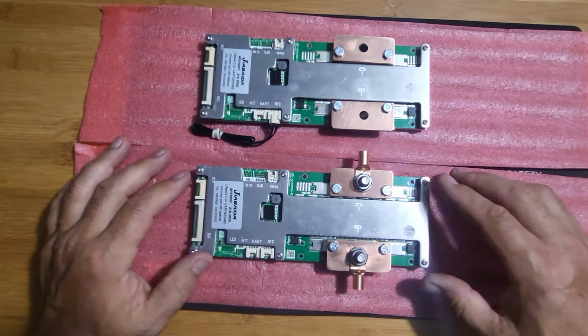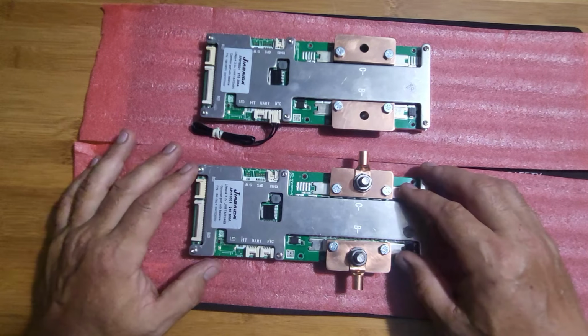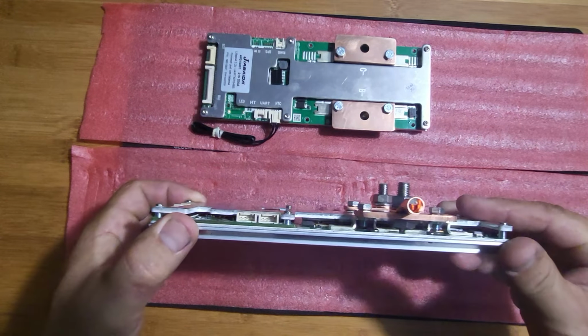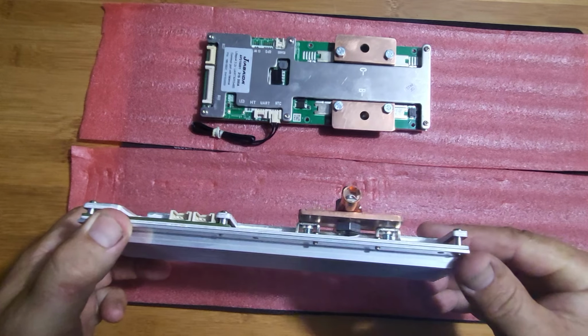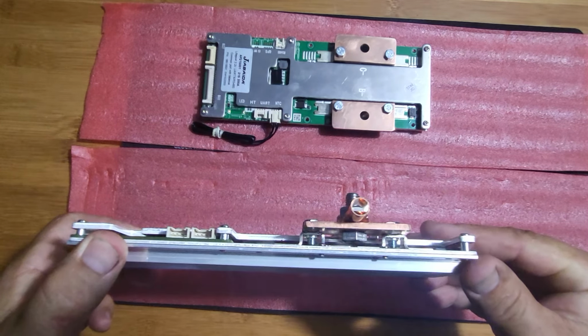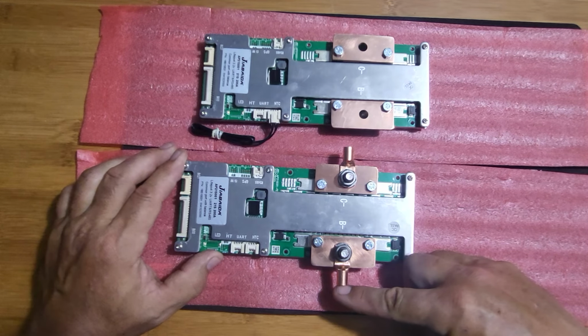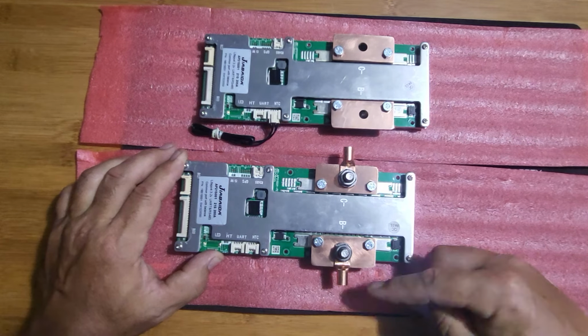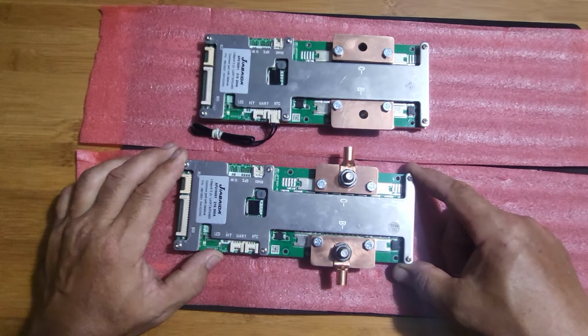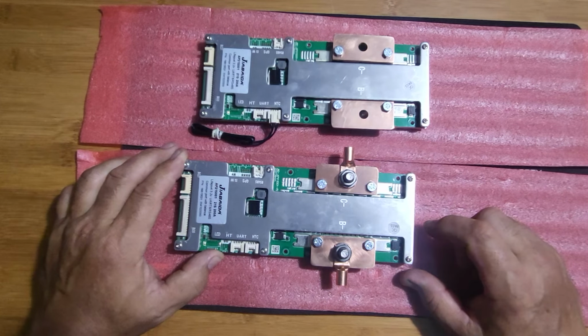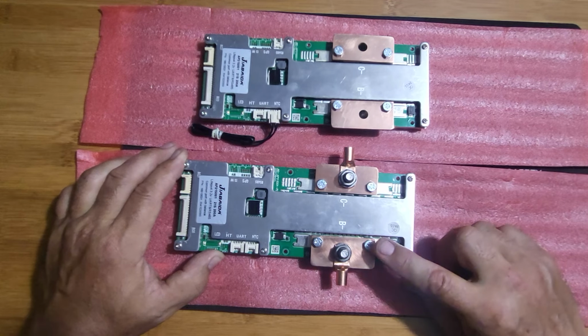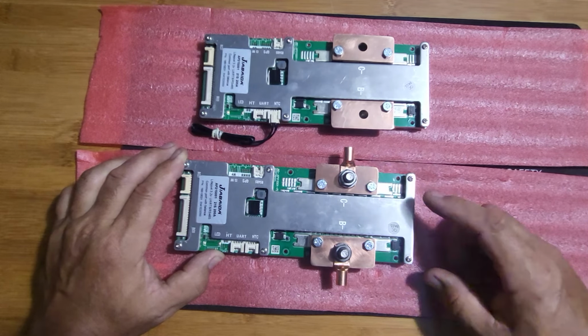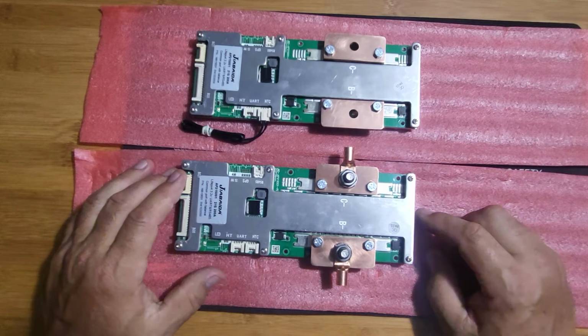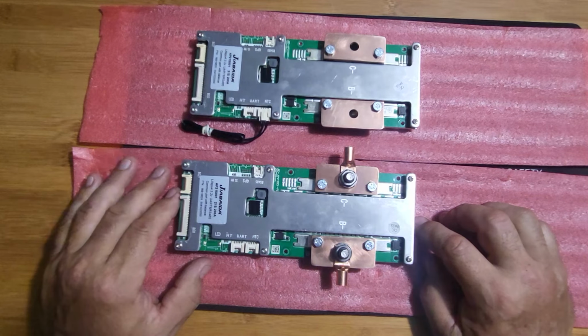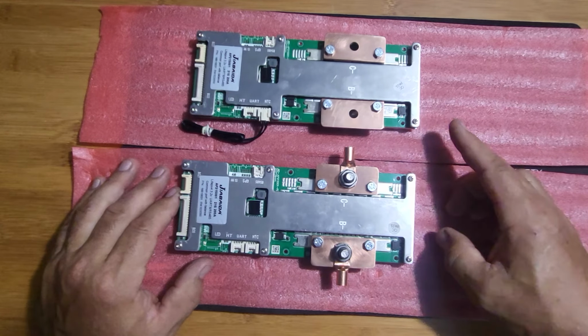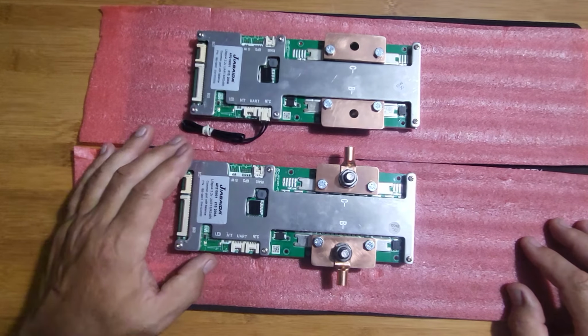All right, this is the JBD BMS with the 2 bus bars that I'm using to jumper between the 2 lugs that come on this unit. So I went with an M8 here. These lugs are a little undersized right now. They're just there to kind of show the concept of what I'm doing here by jumpering the B- and the C- lugs, and then having one larger wire come out of the unit itself. One is going to be 280 amp hour pack, and one is going to be 105 amp hour pack. So I'll size these wires accordingly.